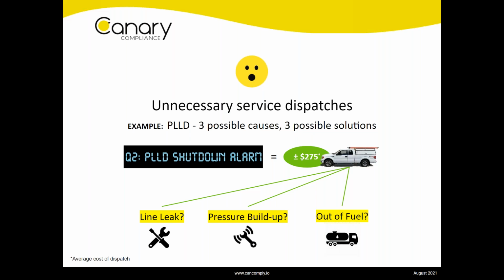The other thing that can trigger this alarm is running out of gas. If you go below a certain threshold in the tank in terms of the volume that's in the ground, you can actually trigger this type of alarm. In that case, obviously, you don't need a service technician, you need a fuel delivery. And that's one of the more common instances that we see, where someone on site sees that the pumps have shut down, they call a service technician, the technician arrives, does some investigative work, and an hour and a half later, while they're billing you the whole time, they determine that there's not enough gas in the ground to keep the dispensers running safely, because it would blow out the motor, and so the pump shut down.